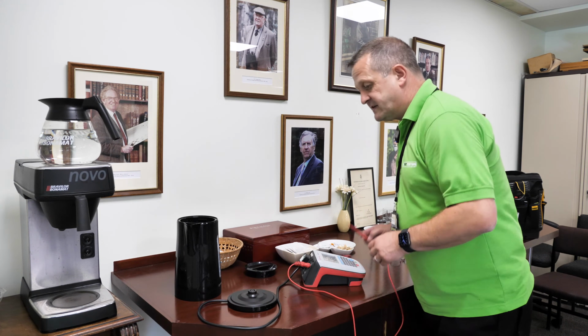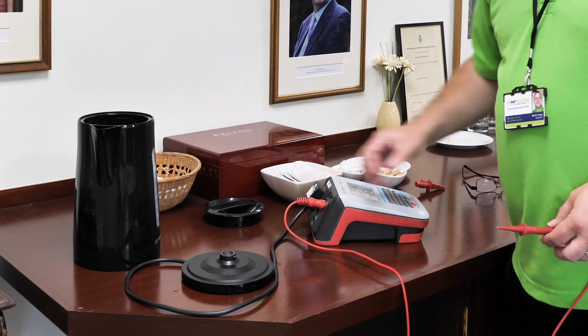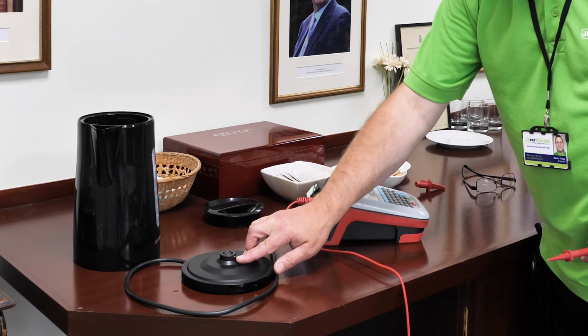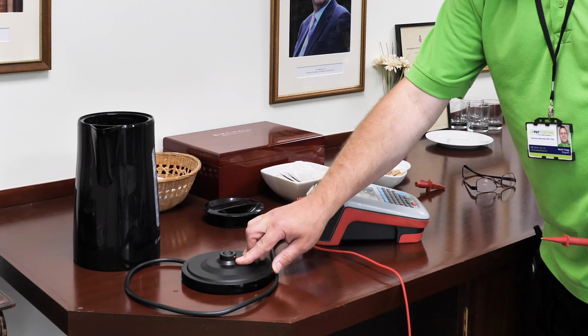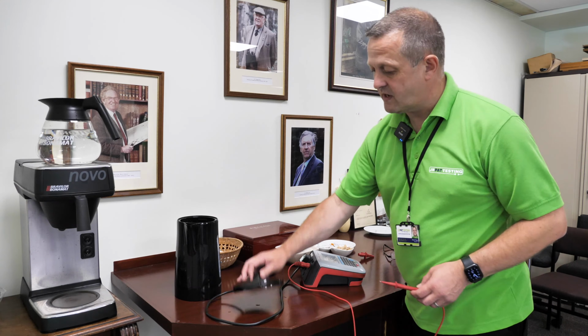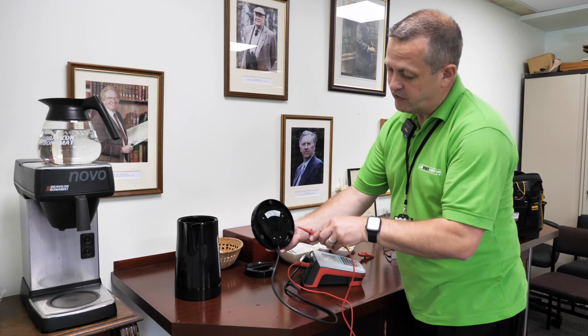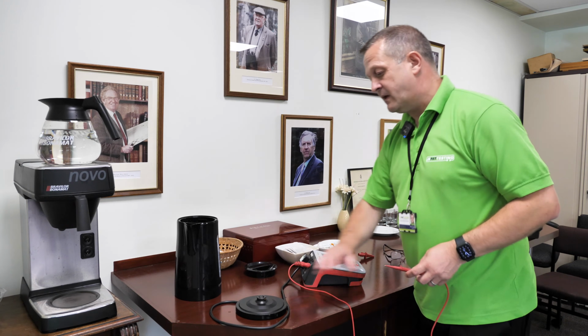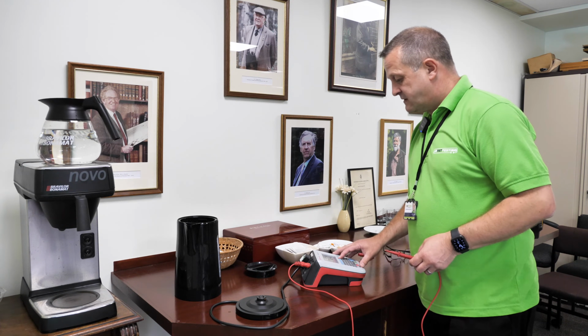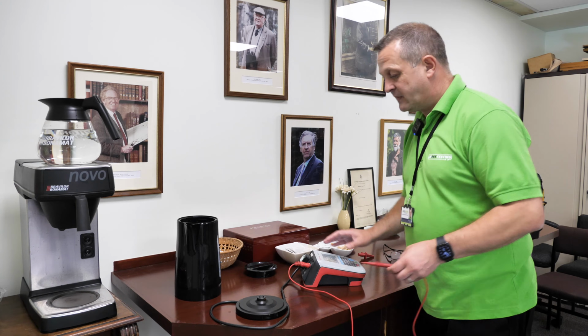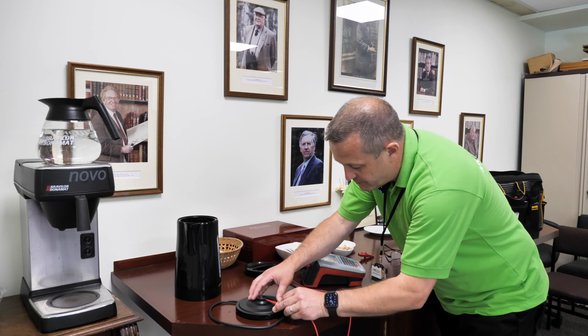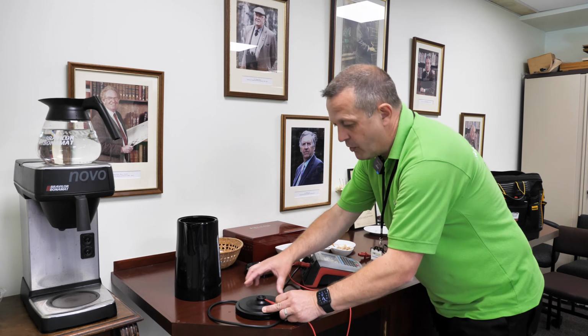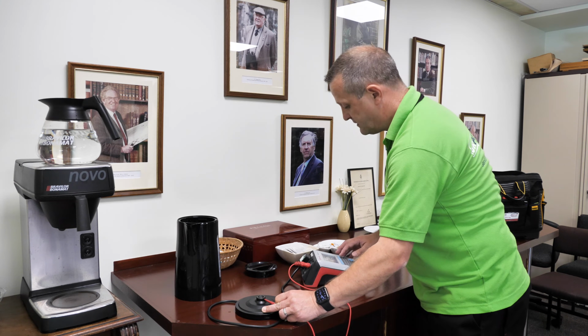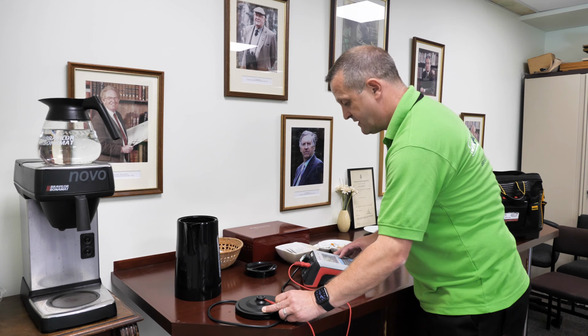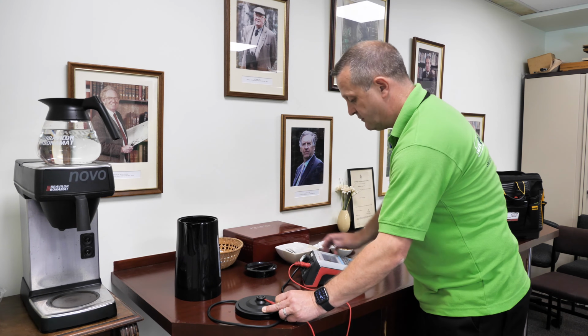In order to get on this type of kettle base an earth contact, you'll just see this little copper prong that comes out of the base. If there's not one on the side, there's usually one underneath where you can shove a prong in. So then we're going to select a class 1 test, and then all we're going to do with the probe is just push that copper prong in order to get that exposed metal contact, and then we're going to test the lead and the base.